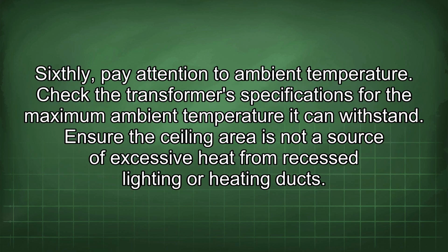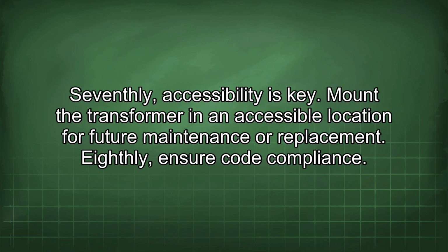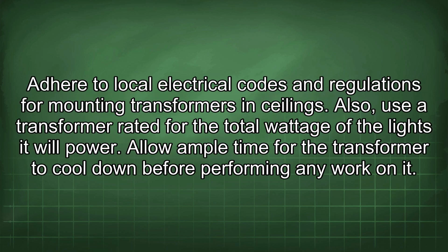Sixthly, pay attention to ambient temperature. Check the transformer specifications for the maximum ambient temperature it can withstand. Ensure the ceiling area is not a source of excessive heat from recessed lighting or heating ducts. Seventhly, accessibility is key. Mount the transformer in an accessible location for future maintenance or replacement. Eighthly, ensure code compliance. Adhere to local electrical codes and regulations for mounting transformers in ceilings.